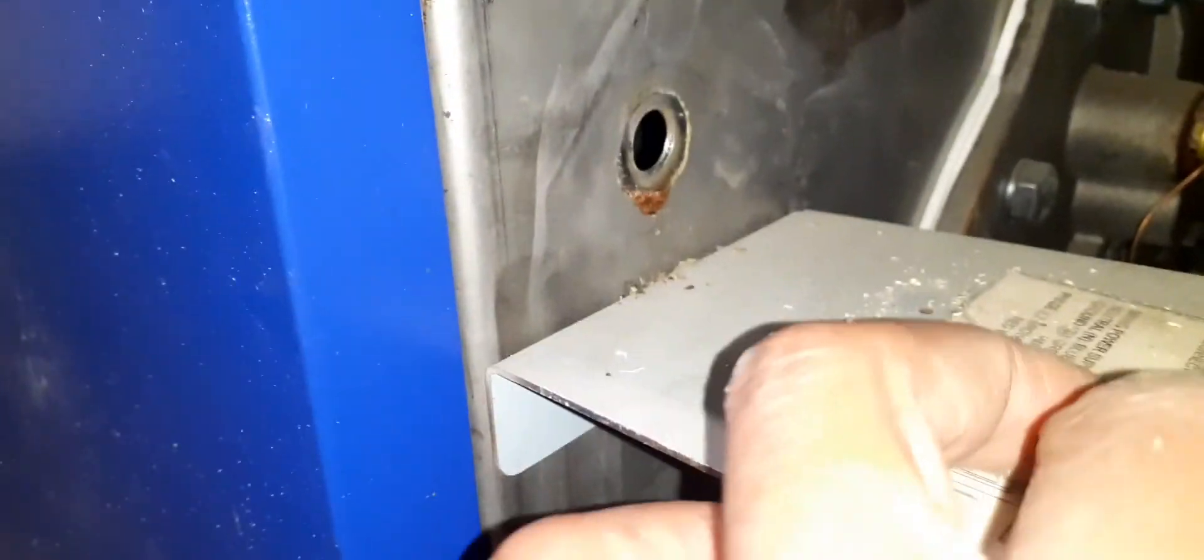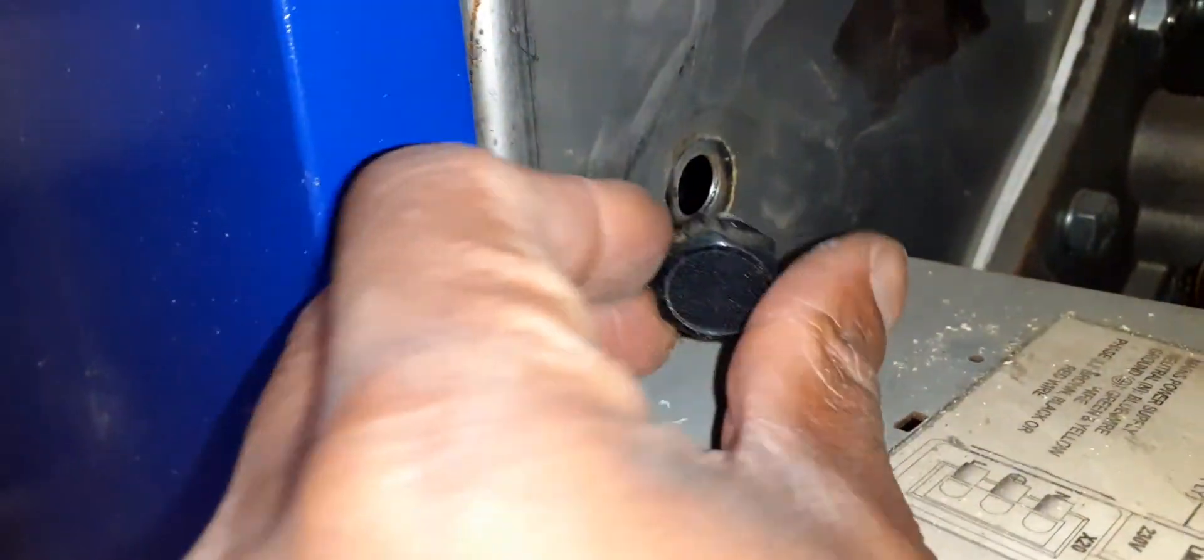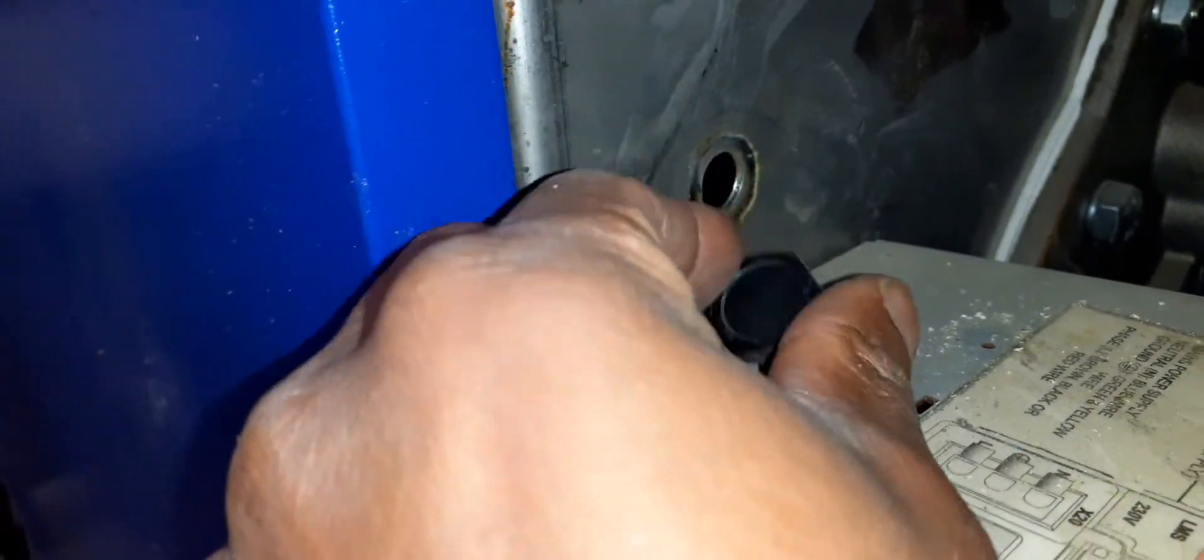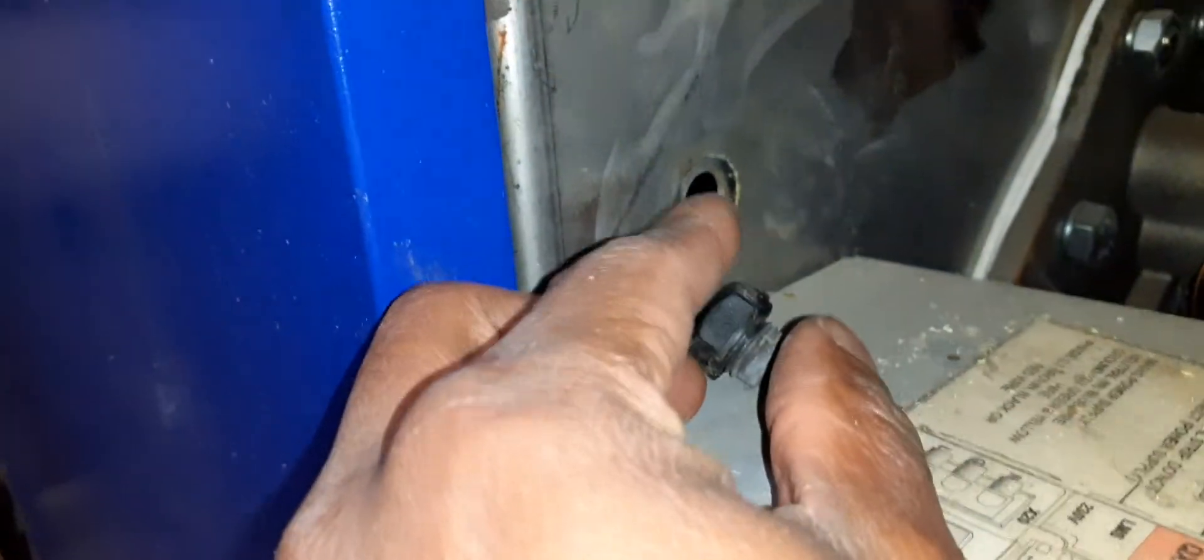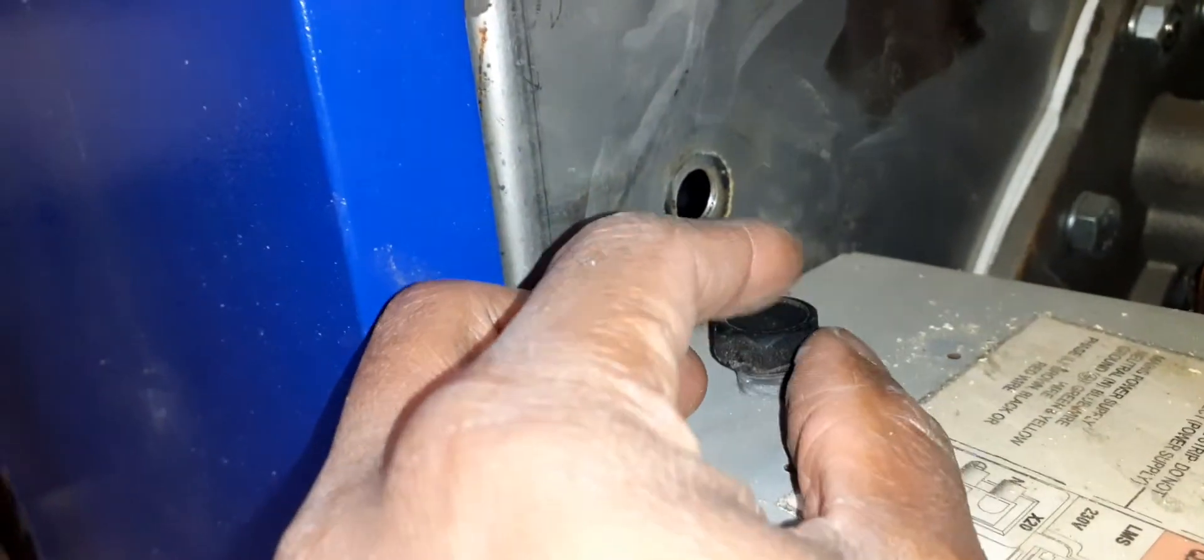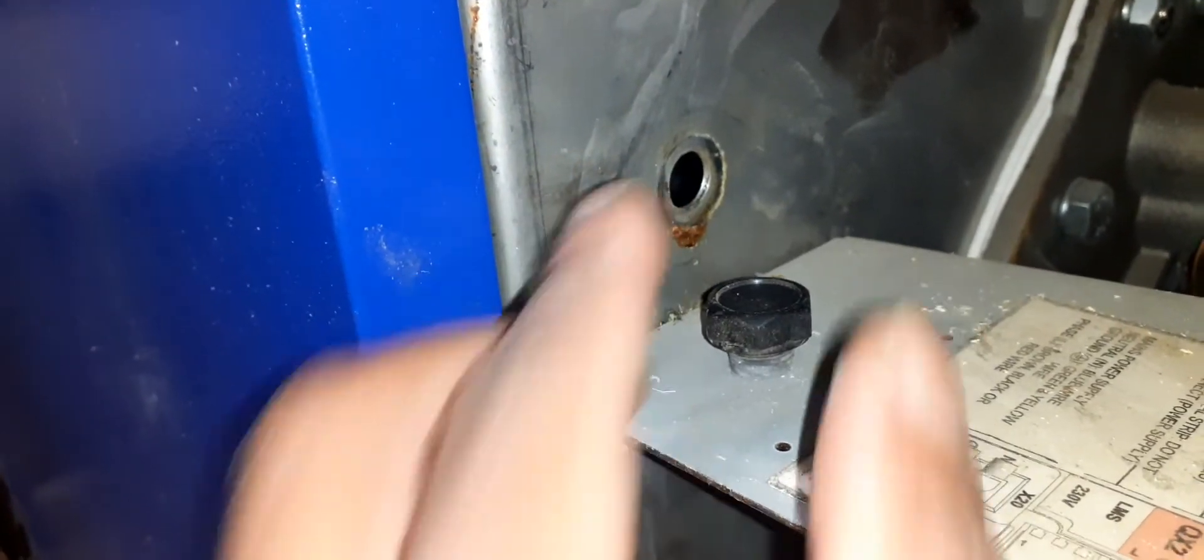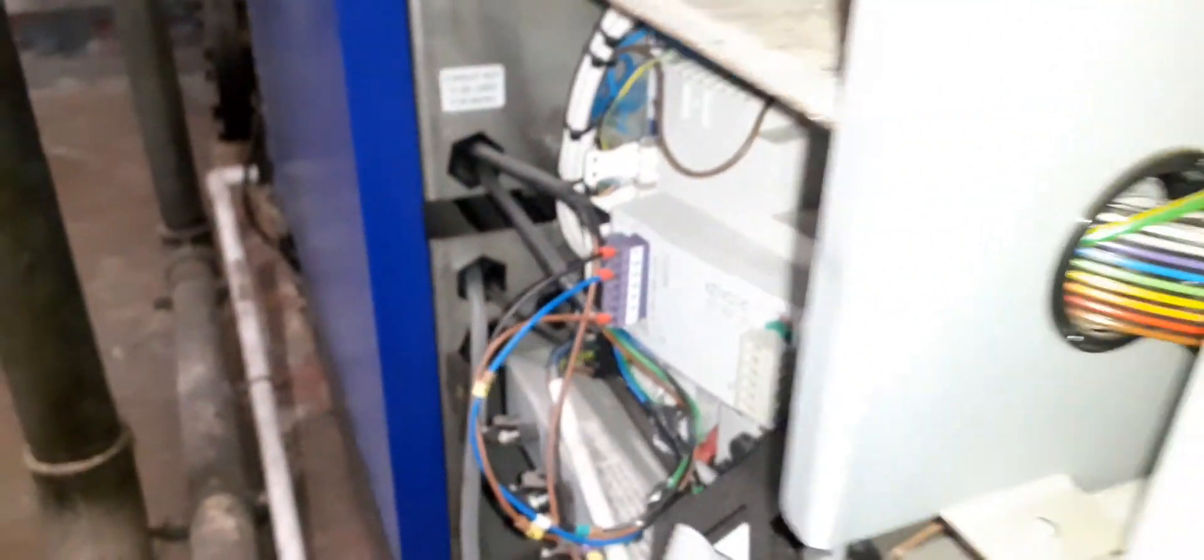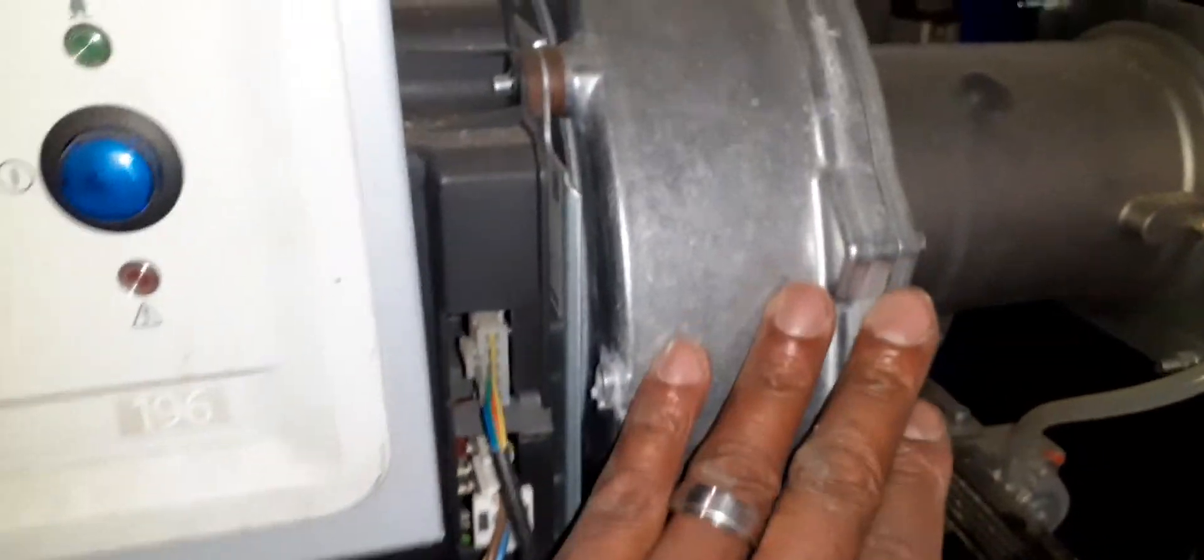Pressure switch. This is our test point, our flue gas analyzer test point. Always remember to check that these go back on after checking your combustion. Our fan.